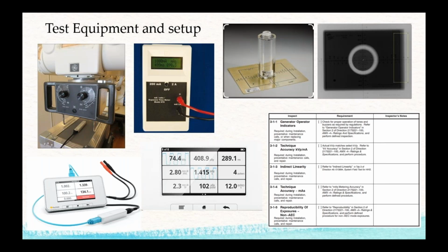To do that, we have these different manufacturers out there, but I happen to carry around a RaySafe X2, and it's plug and play: turn it on, put the probe in, take the shot. It's displayed. It even gives you the kV waveform on this particular device if you slide some screens. But anyway, what I'm going to do is set the generator at 75 kV at 10 mAs. I'm going to take the shot.